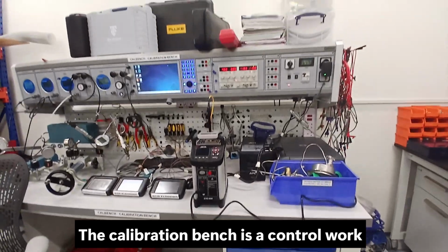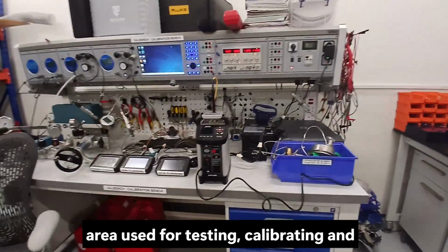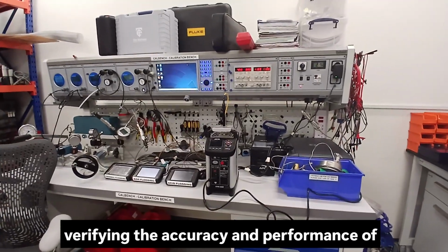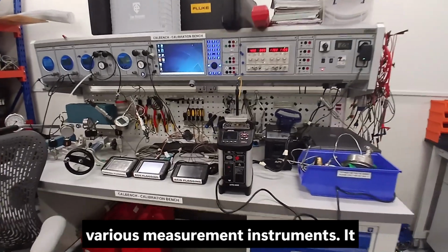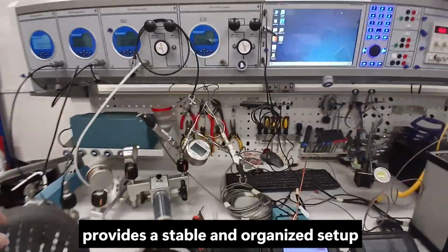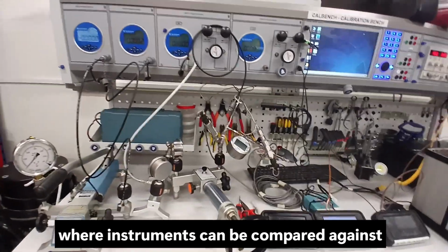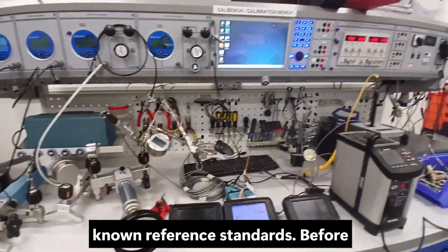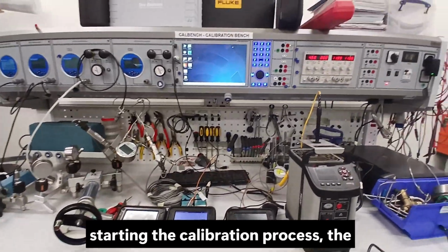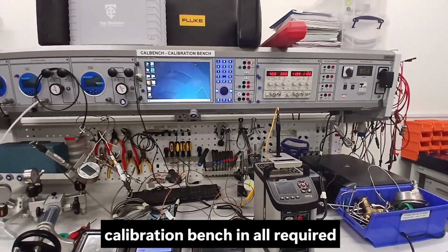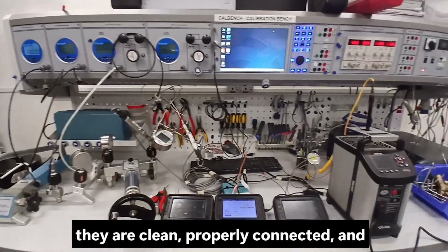A calibration bench is a control work area used for testing, calibrating, and verifying the accuracy and performance of various measurement instruments. It provides a stable and organized setup where instruments can be compared against known reference standards. Before starting the calibration process, the calibration bench and all required equipment are inspected to ensure that they are clean, properly connected, and in good working condition.